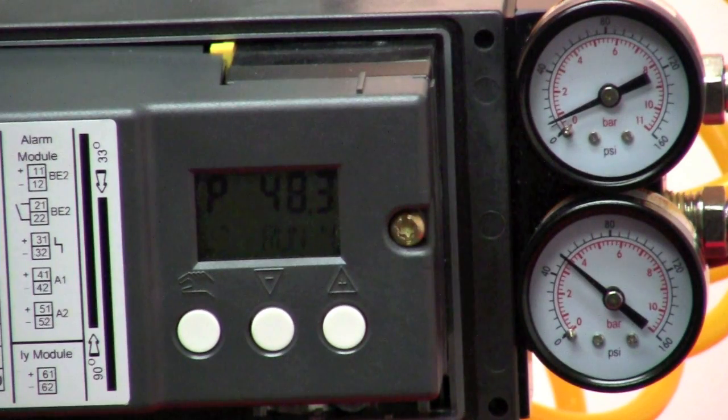Run 1 establishes the direction of operation. Run 2 establishes the end points of the stroke, where is the valve fully open and where is it fully closed.